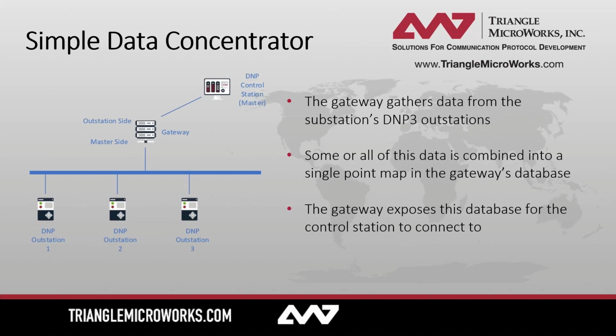So let's take a look at a very simple system. This is our simple data concentrator system. In this situation, we have several DNP outstations in our downstream substation, and we also have a DNP control station upstream. What we're going to do is gather some or all the data points inside of these DNP outstations and combine them into a single gateway database. This database is then exposed up to the control system, so that the DNP control station can actually see all the variables and data stored within all the outstations beneath.